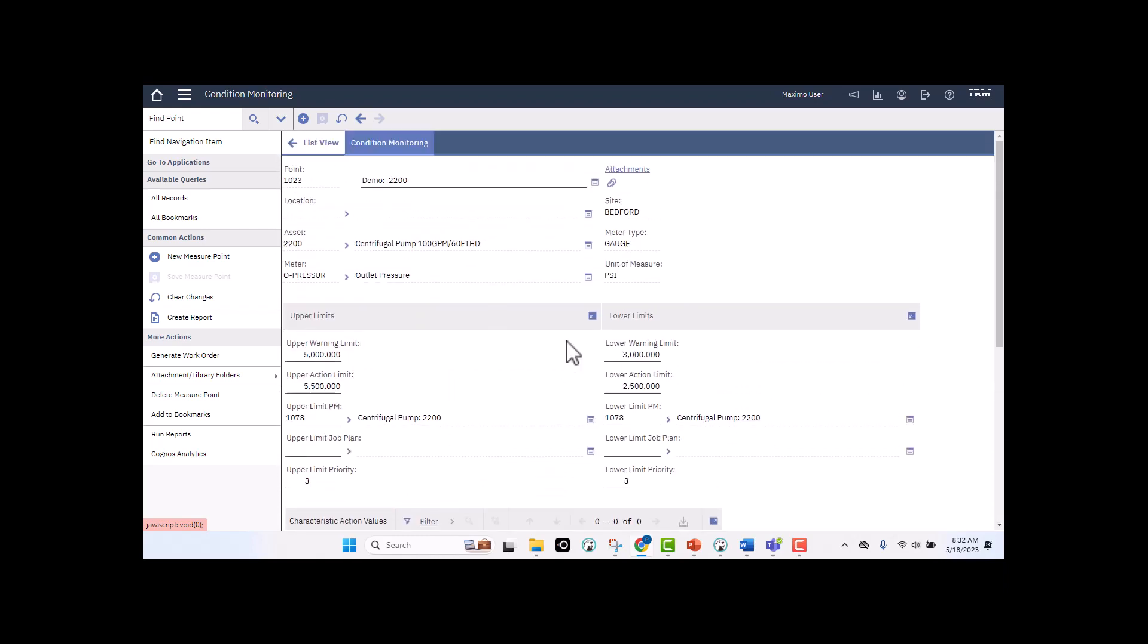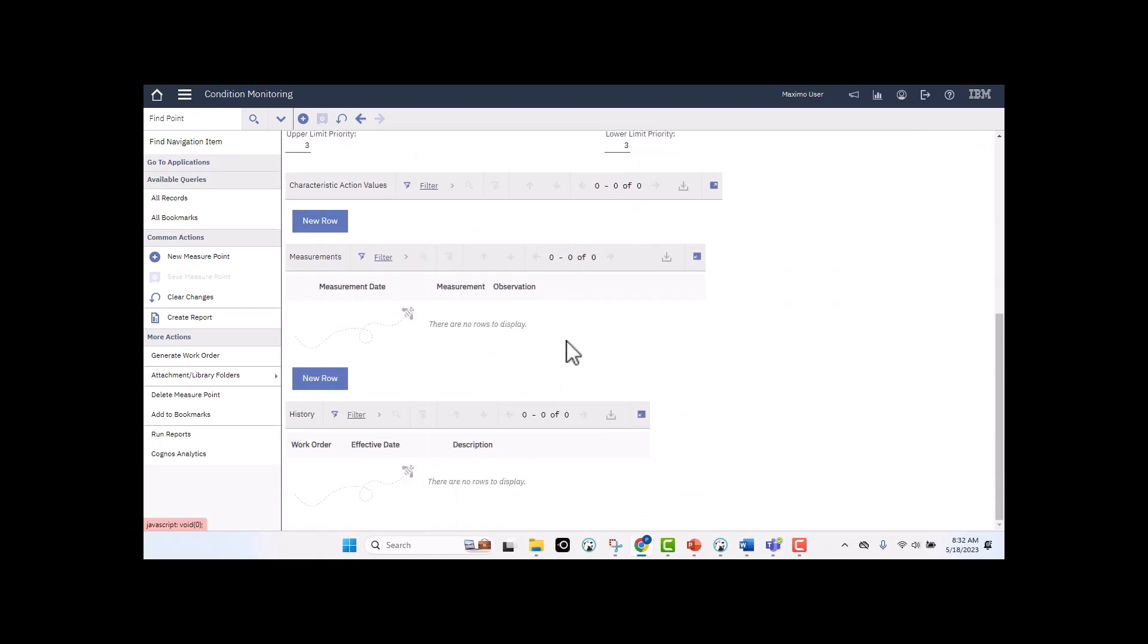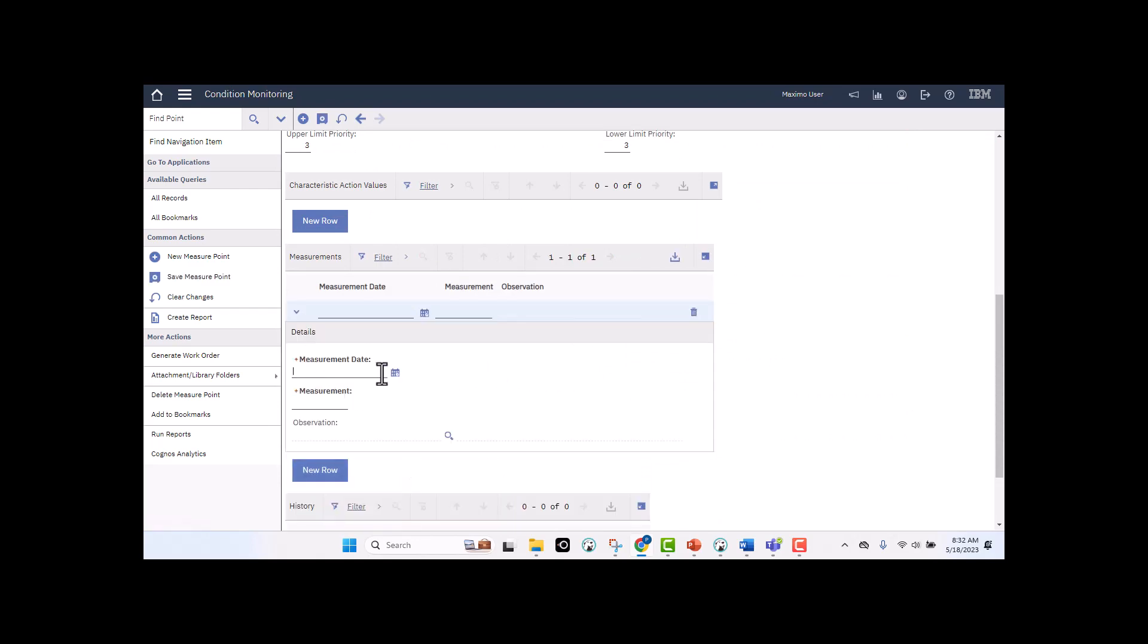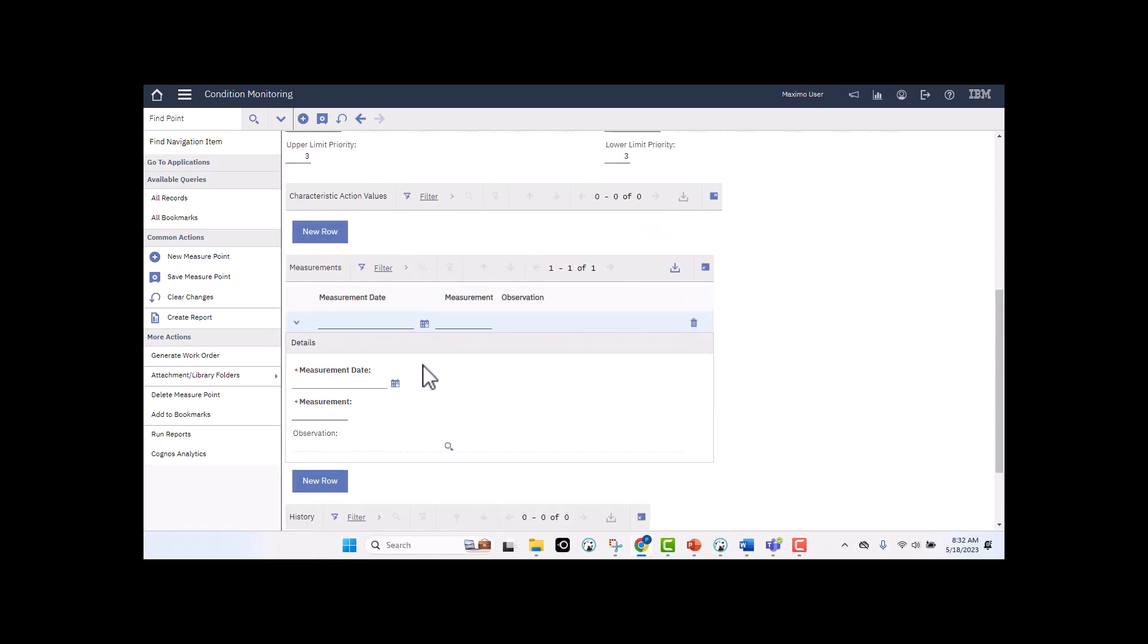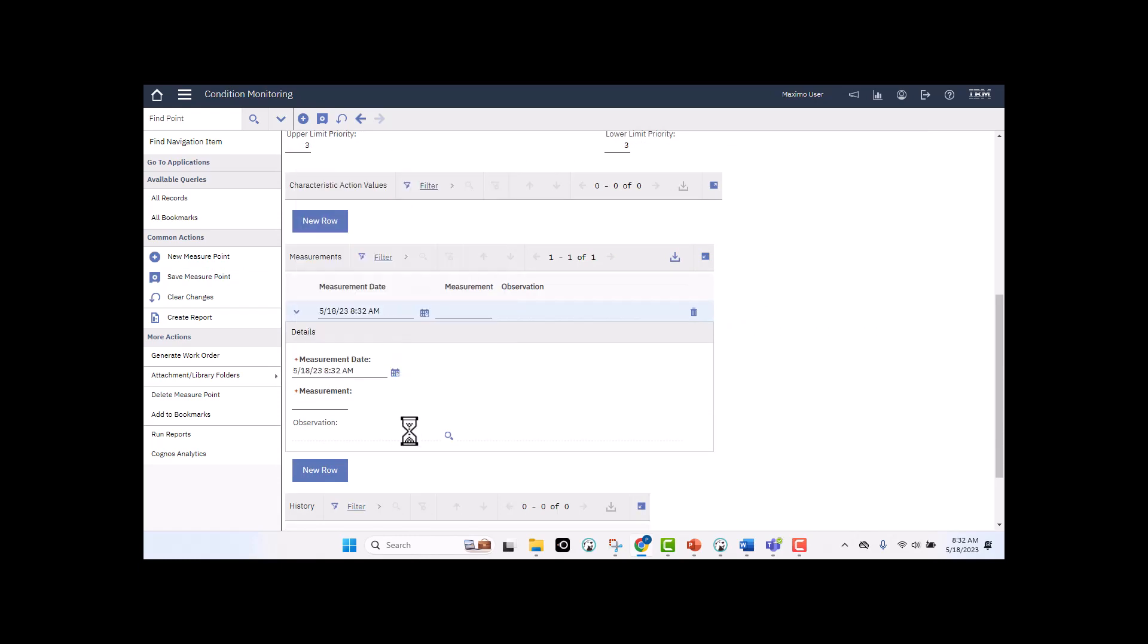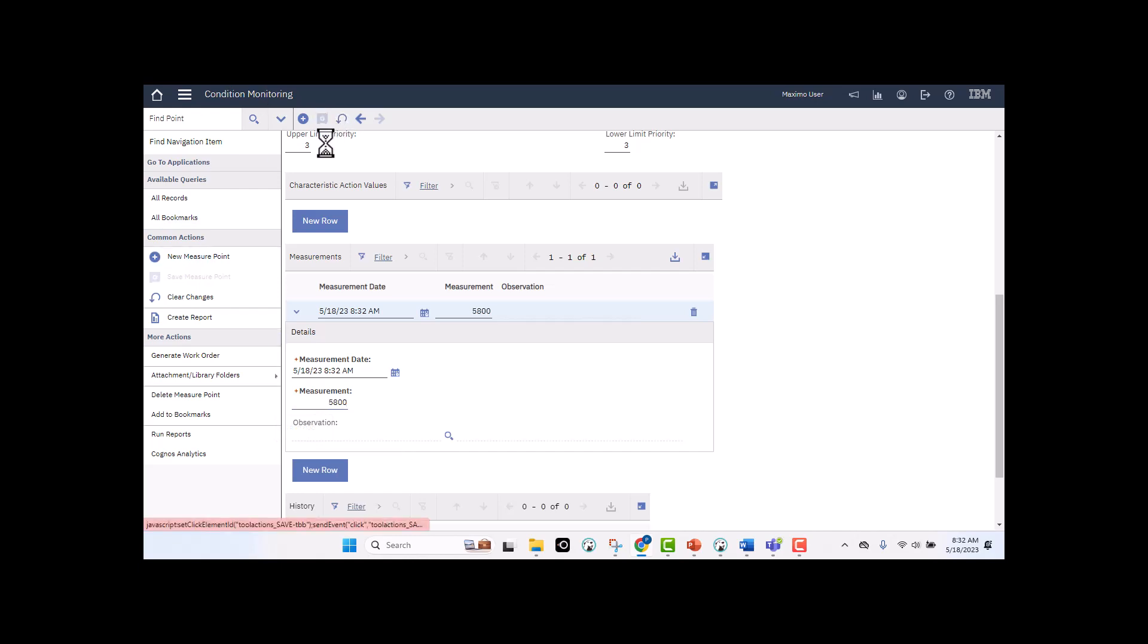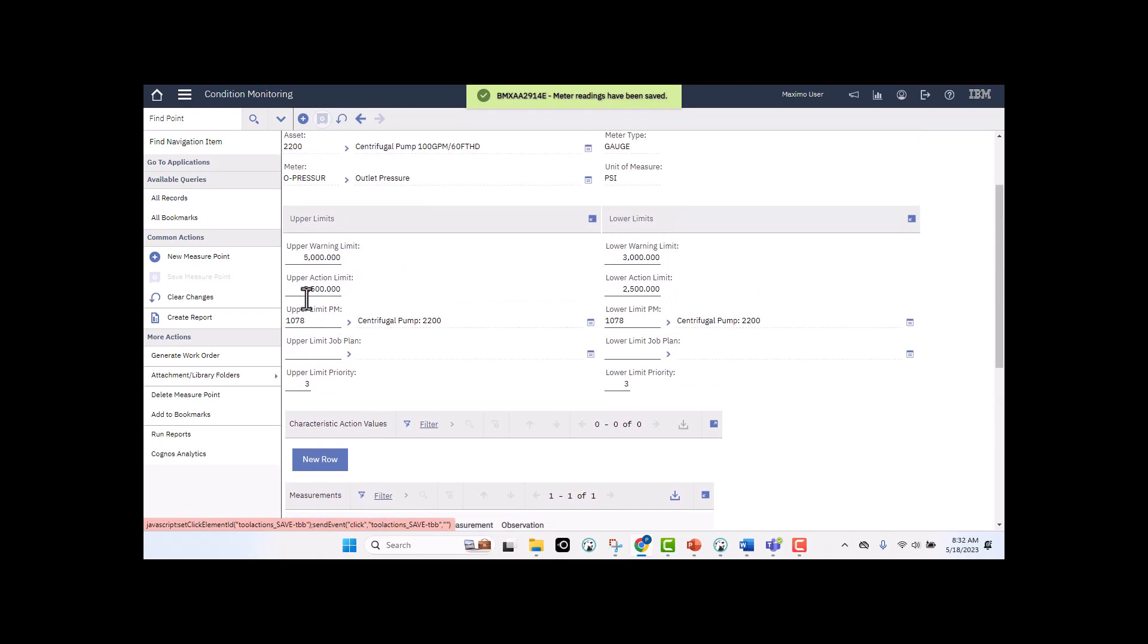But now, what Condition Monitor also enables me to do is I want to test this, I want to make sure that I can have this point kick off an incorrect value, or a high warning value. So the beauty about Maximo demo data is I can put in anything I want here to test this. I'm going to put in a high value at 5800. So that's my pressure reading. So again, with a value of 5800 that I see here, it should automatically kick off that cron task and have my work order generated.